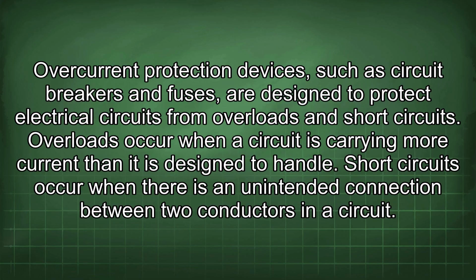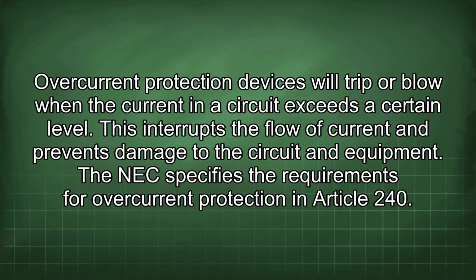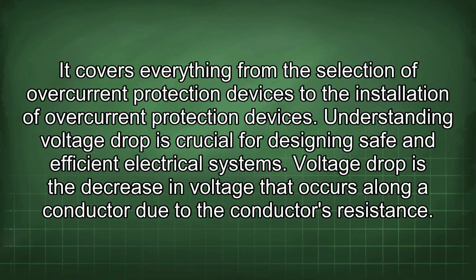Overloads occur when a circuit is carrying more current than it is designed to handle. Short circuits occur when there is an unintended connection between two conductors in a circuit. Overcurrent protection devices will trip or blow when the current in a circuit exceeds a certain level. This interrupts the flow of current and prevents damage to the circuit and equipment. The NEC specifies the requirements for overcurrent protection in Article 240. It covers everything from the selection of overcurrent protection devices to the installation of overcurrent protection devices.